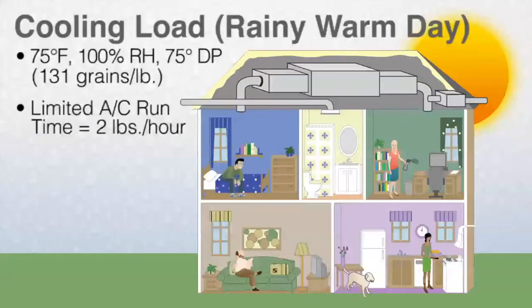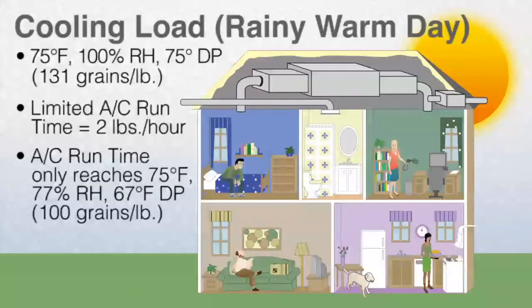The worst case scenario is that in green grass climates, we have rainy warm days mixed in with hot dry days. On a rainy warm day, assuming 75 degrees and 100% RH — it's raining — we've got a 75 degree dew point and 131 grains of moisture per pound of air that infiltrates that home, plus moisture from the occupants. The AC is running quarter time, similar to the night, removing two pounds of moisture per hour. This gets us to 75 degrees and 77% RH, a 67 degree dew point, and 100 grains per pound of the inside air — which means we've got a damp house.